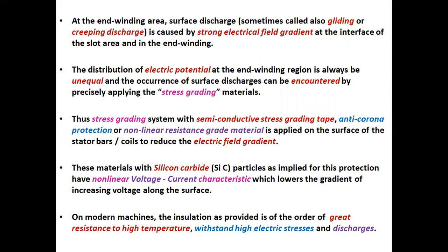Thus, a stress grading system with semiconductive stress grading tape, anti-corona protection, or nonlinear resistance grade material is applied on the surface of the stator bars or coils to reduce the electric field gradient. These materials, with silicon carbide particles, have a nonlinear voltage-current characteristic which lowers the gradient with increasing voltage along the surface.